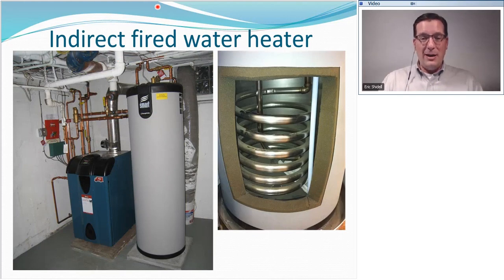Deep inside of the water tank is a heat exchanger, and this is where the boiler water is flowing through this coil, and it is surrounded by the domestic water in the tank. So this acts kind of like the heating element in an electric water heater. This is the heating element. So we've got hot boiler water circulating through here. Meanwhile, the domestic water surrounds it and is being heated by the boiler.